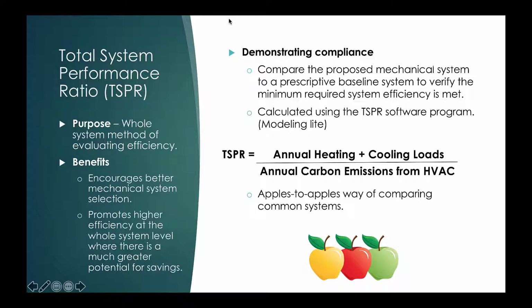To demonstrate compliance with the TSPR requirement, the designer compares their proposed mechanical system to a prototype prescriptive baseline system. This is done using the new TSPR software program developed by the Pacific Northwest National Labs. Think of it as modeling light, accomplished with a user-friendly tool that does not require modeling expertise to use. The tool calculates the annual heating and cooling loads divided by the annual carbon emissions of the HVAC system. This provides an apples-to-apples way of comparing common systems.